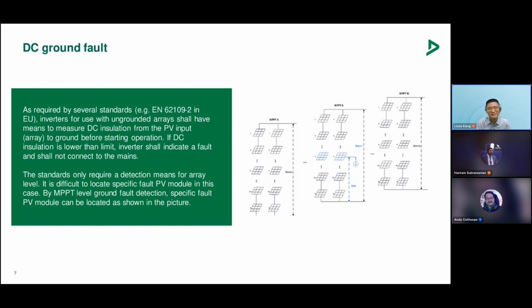Currently, product testing standards do not require any means for detecting exactly which PV string or which PV module has a fault. But we can go further than what the standard requires. If we have an MPPT level fault detection technology, it can directly localize the fault PV string and could infer which PV module has a fault by calculating from DC insulation resistance. We will be able to find the fault PV module much more easily. This could be a future trend for DC ground fault.